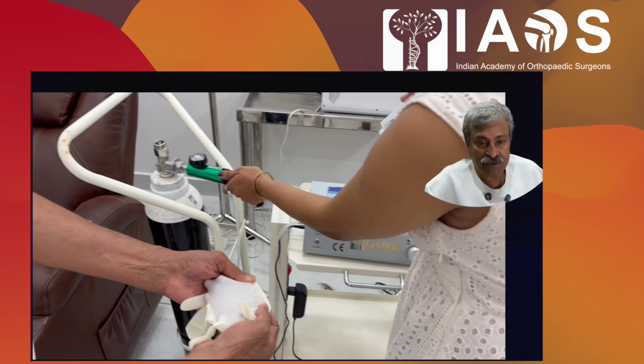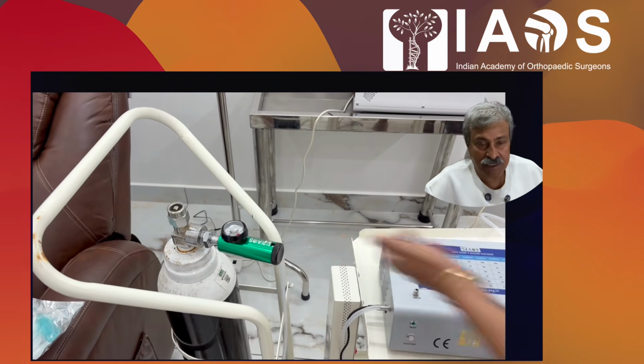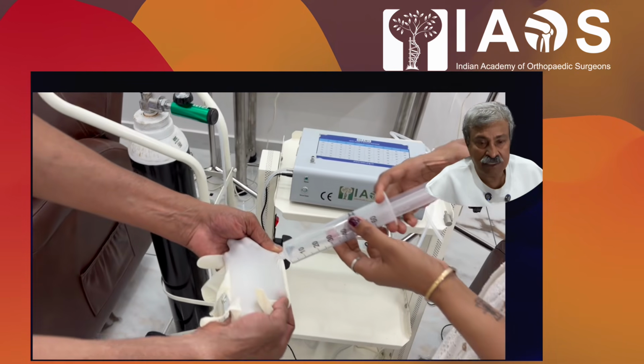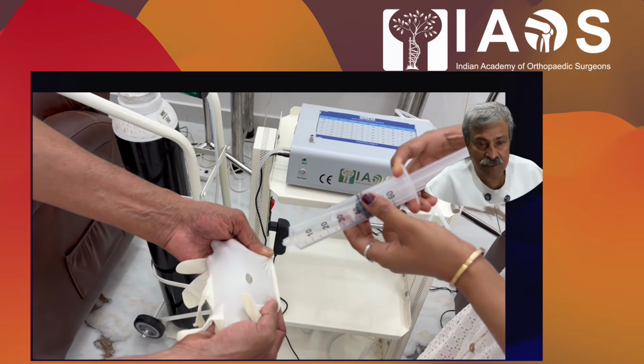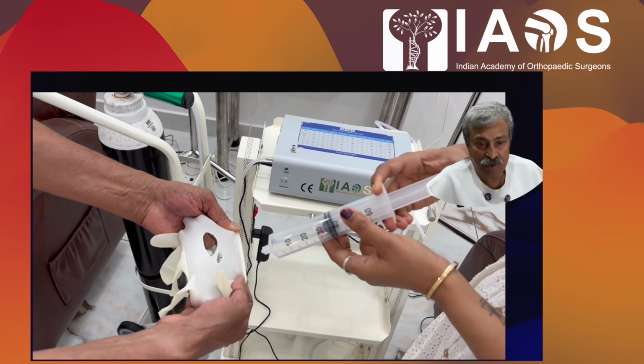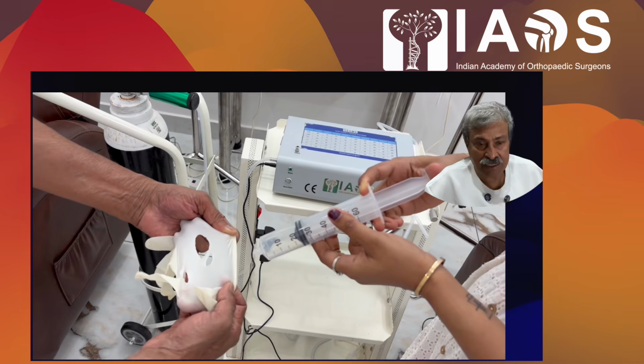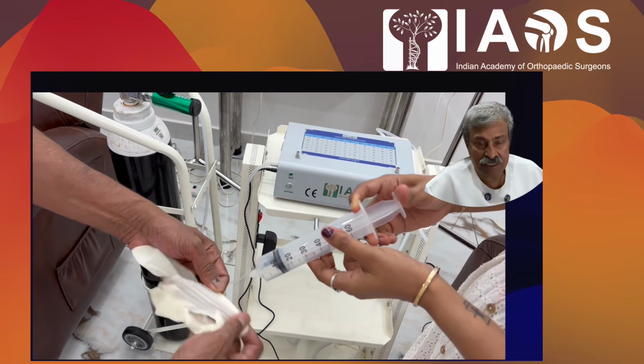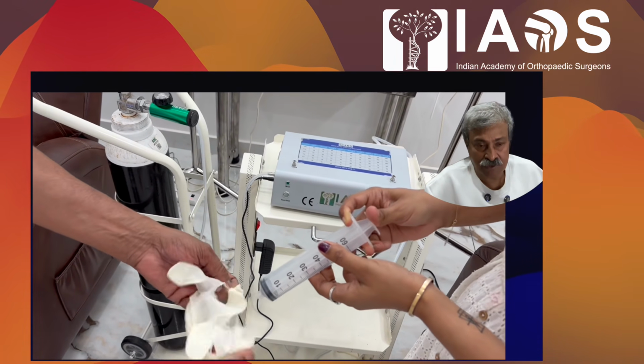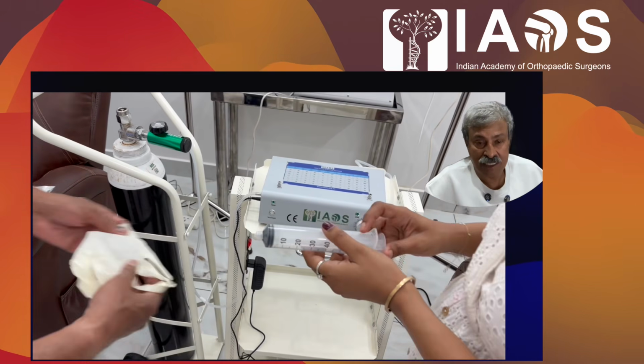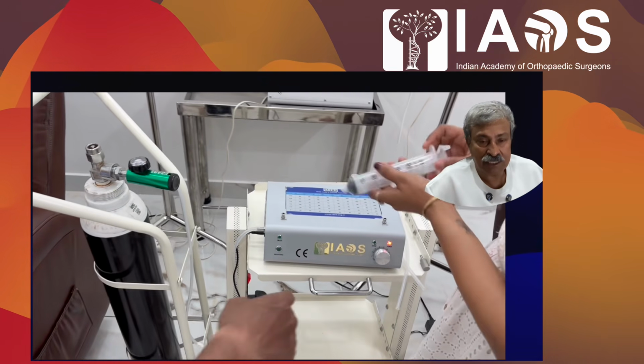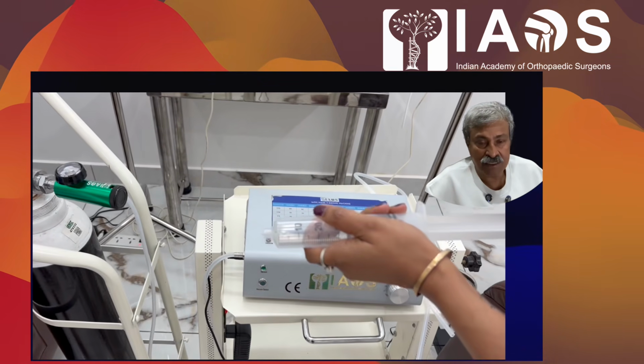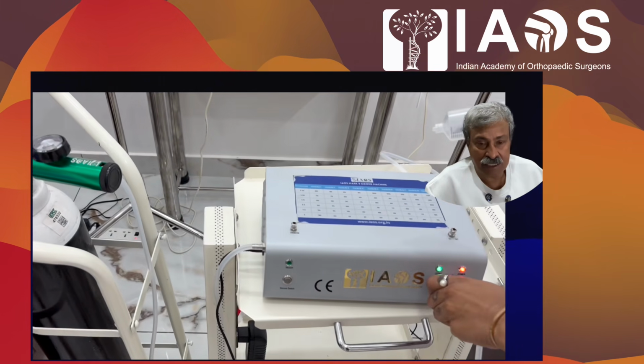To test whether the ozone is proper and concentrated, we will just blow it on a glove, and we can see that holes are made. This is called a latex test, and even a slight touch of this sort of ozone will melt the latex. We should thus be very careful in using rubber and plastic containers.